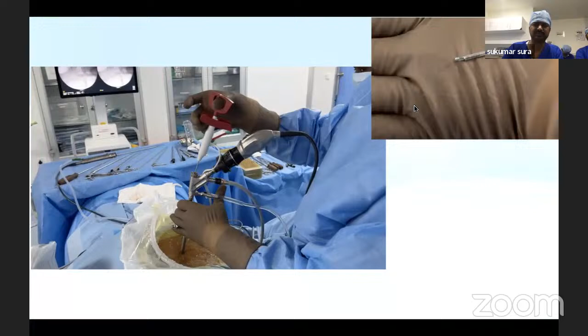Usually the settings we keep are around 20-20 for coagulation and cutting. That is enough. Some people keep 30, and ultimately when you want to shrink more, they keep 40. So what happens beyond 20? The coating around the bipolar probe goes away. The insulation goes away, and it becomes less effective because the spread of current becomes more. And in the next cases, when you want to do a focal coagulation, you can't do it. So the probe, if you use it carefully, can be used for 8 to 10 cases.